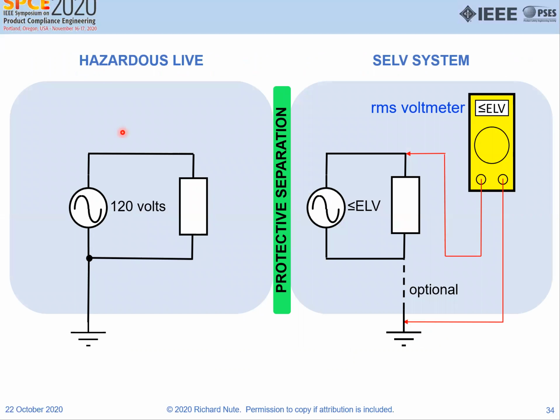So here we have the hazardous live circuit. And we have protective separation between the two, between here at this point. And we have the lower than ELV. This may very well be the secondary of a transformer, and this may be the primary of the transformer. But you have to have protective separation. The voltmeter measures the voltage at less than ELV.